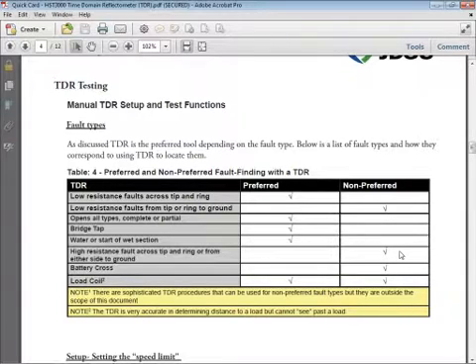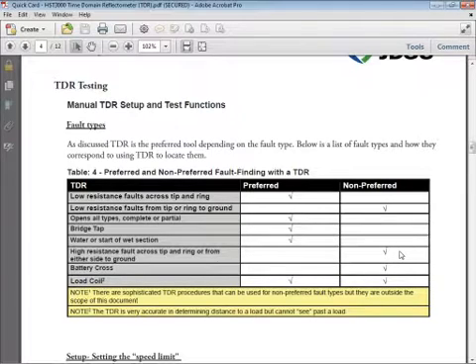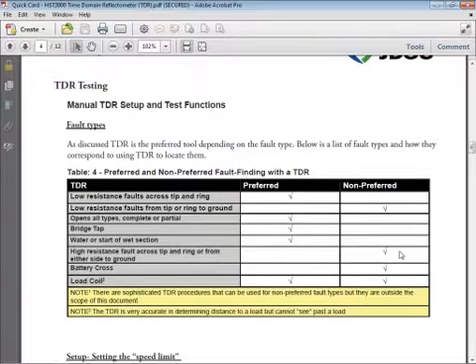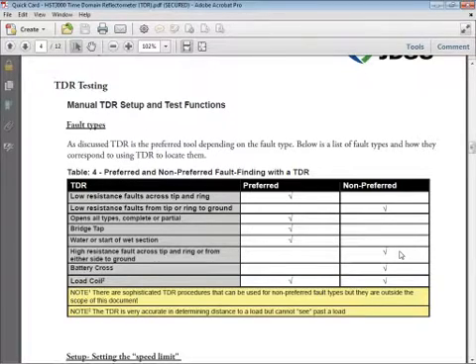Bridge tap — the only thing out there that I know of that will show you the start of the tap, and if you're lucky, even show you the end. Water, or start of a wet section — probably should have a check mark in both columns here. The TDR is quite good at showing you the beginning of a wet section. However, if your fault is on the other side of the water, the TDR loses a great deal of its accuracy. The reason is water will slow down the speed of the signal — anything that messes with the speed messes with the timing. Time is distance in the world of the TDR, so water will affect accuracy. Aside from a high resistance open, that's the only high resistance thing the TDR can do. It's not going to find a high resistance short, a high resistance ground, or a high resistance battery cross — not with the TDR. That's why you still have RFL capability built into your meter.